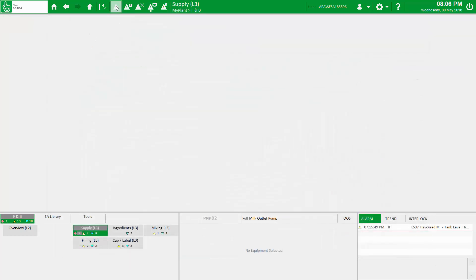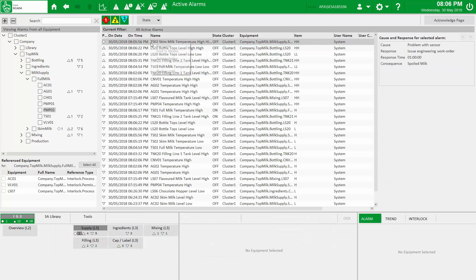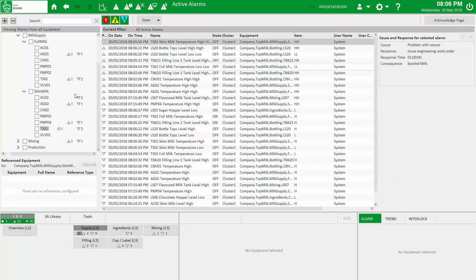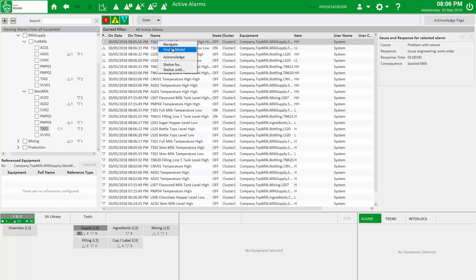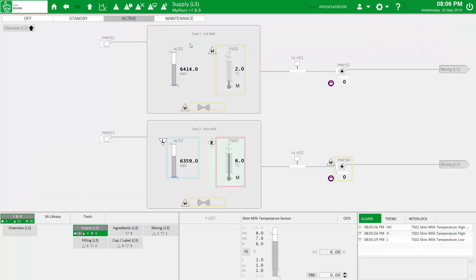We've updated the alarm page as part of the new layout, which includes the ability to apply alarm filtering by the equipment hierarchy or just by severity, and direct access to up to eight sets of alarm cause and response information. The alarm page also includes workspace navigation, meaning you can move directly from the alarm page to the relevant workspace overview page with the item selected for you automatically.